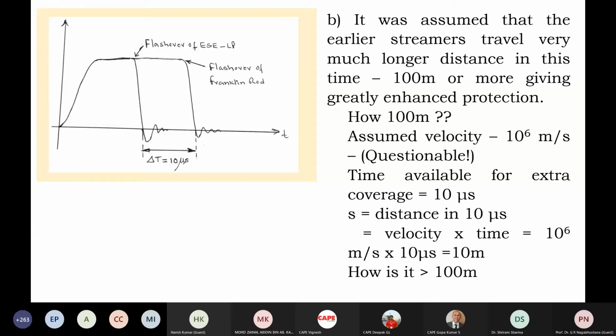But they have assumed that the earlier streamers travel a very much longer distance in this time, 100 meters or more, giving greatly enhanced protection. How did they arrive at this 100 meters? They assumed a velocity of 10 to the power 6 meters per second, which is highly questionable. The time available for extra coverage, according to them, is 10 microseconds, which is the time differential between the flashover timings of the flashover wave shape for the ESE and for the Franklin rod.